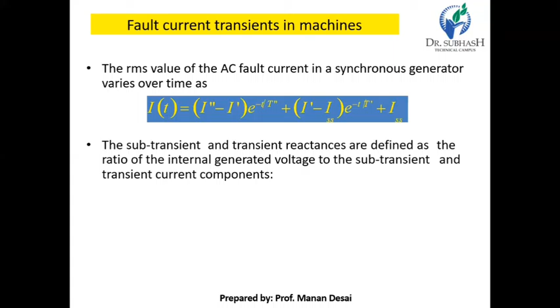The AC current flowing in the generator during the transient period is called the transient current, and it is denoted by I dash. The time constant of the transient current is denoted by T dash. This current is often as much as 5 times the steady state fault current. So in the transient period, the current falls slowly, from 10 times the steady state fault current down to 5 times the steady state fault current.